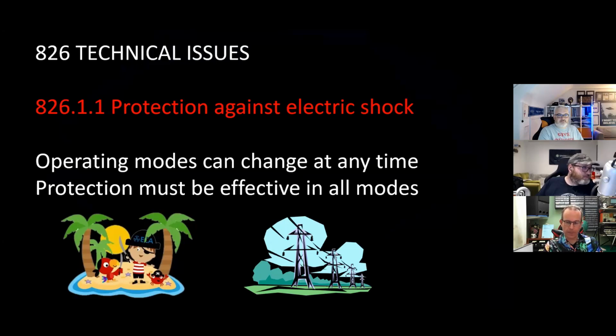Now, the first one of these is that operating modes can change at any time. So remember, this is the island mode or the direct feeding mode or the reverse feeding mode. And protection, as in protection against electric shock, must be effective in all of these modes. Just think about this. It's a little bit like where you have a generator operating as an alternative and you have that automatic switchover. It's a similar idea. The difference here is that it's quite likely on a prosumer installation that it's going to change modes quite often, several times a day, maybe even several times an hour. So whatever protection you put in, as in circuit breakers, RCDs, and whatever else, it's got to work in all of the modes all of the time.